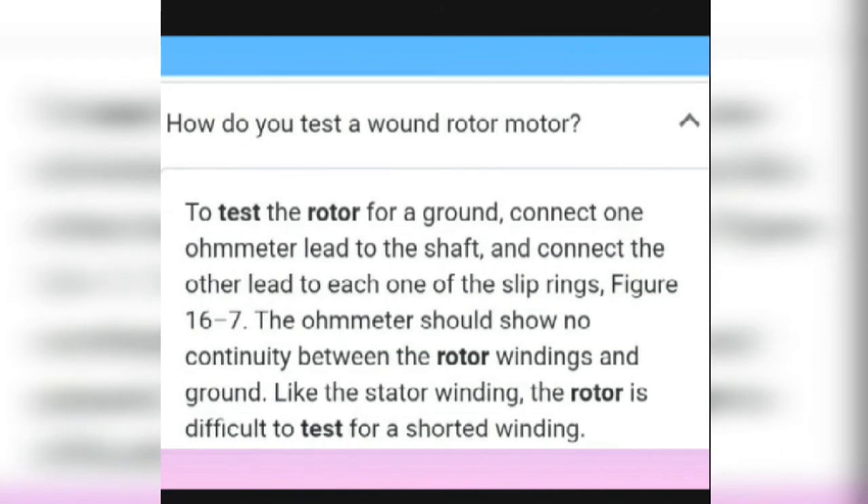To test the wound rotor motor, connect one ohmmeter lead to the shaft and the other lead to each slip ring in turn. The ohmmeter should show no continuity between the rotor winding and ground. Like the stator winding, the rotor is difficult to test for short winding.